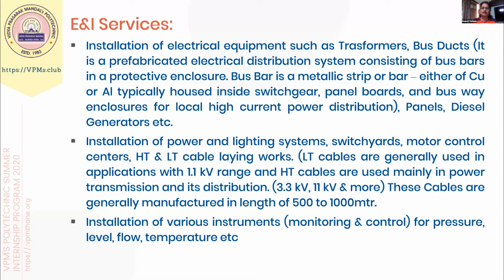Bus duct is a prefabricated electrical distribution system. It's made with metal sheet, consisting of bus bars in a protective enclosure. Bus bar, what is a bus bar? A bus bar is a metallic strip or bar which carries the current. The MOC, the material of construction, is either copper or aluminum, typically housed inside any switchgear or busway or the bus duct, which carries local high current power distribution. For power distribution, it is used.